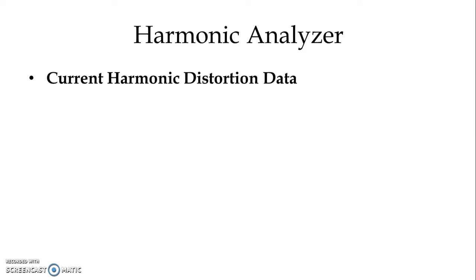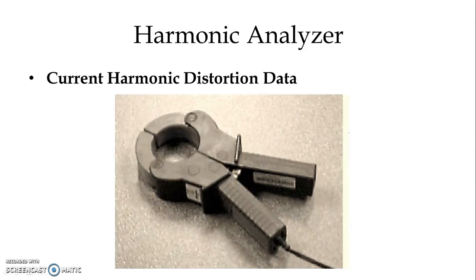We also have current harmonic distortion data. In the figure we can see the current probes which we use to measure current harmonic distortion data. Normally, in current probes we use an iron core type transformer and we can easily measure the harmonic distortion in any conductor. We have to take care that the iron core type transformer gives error at higher frequencies, and when the current exceeds the rated value it goes into saturation, giving a very non-linear output with error.